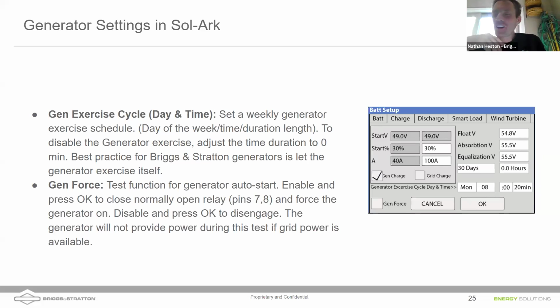Go ahead. I've got another great question that comes in here from Jeremy Zinn. Hi, Jeremy. Welcome back to one of our trainings. Love having you on. Jeremy says, if you have a non-2-wire start generator, a 20 kilowatt Briggs that is older, I would manually turn on the gen as needed during a power outage. When this generator exercises each week, will it cause an error on the inverter when it senses the power from the generator? I'll answer that quickly, Jeremy.